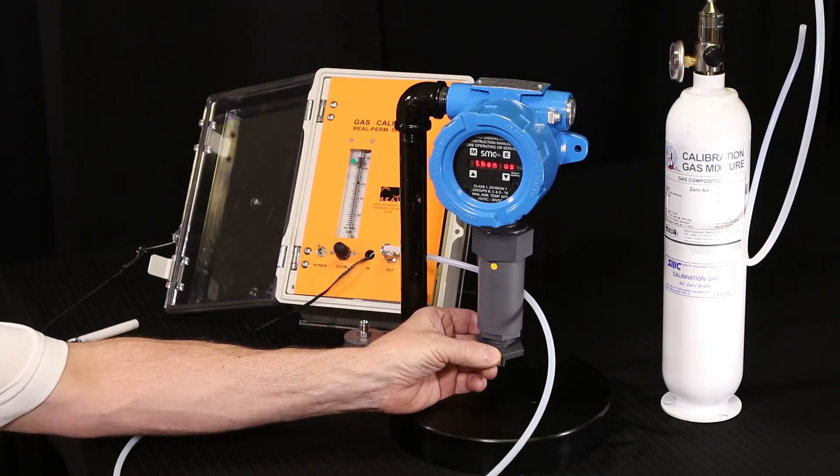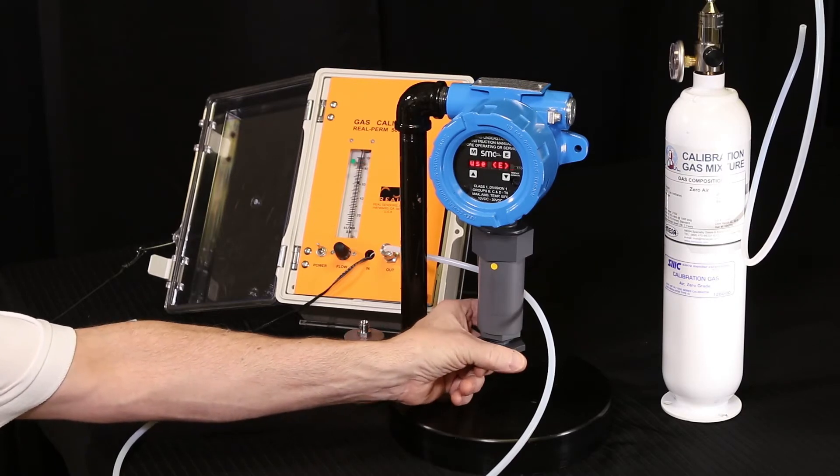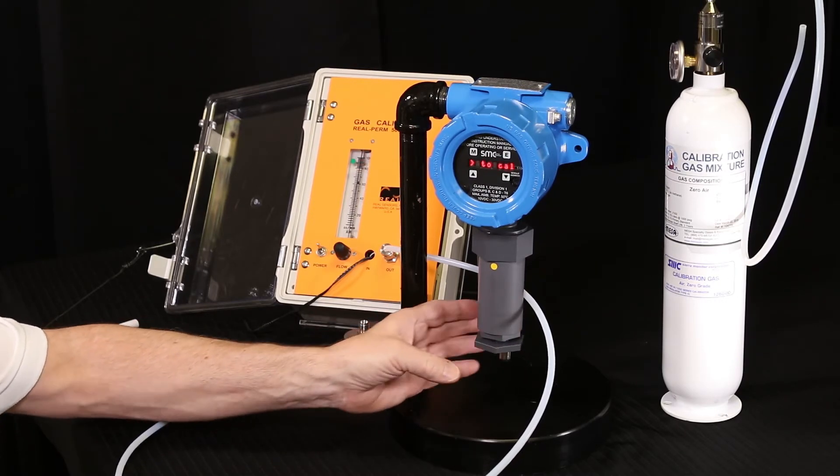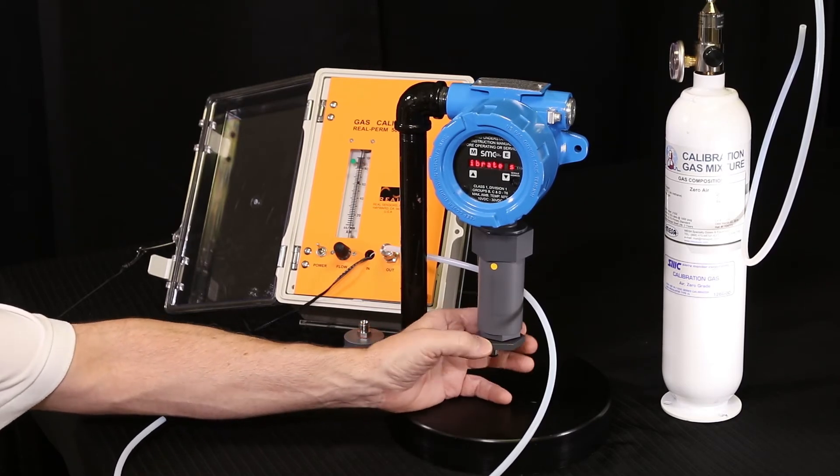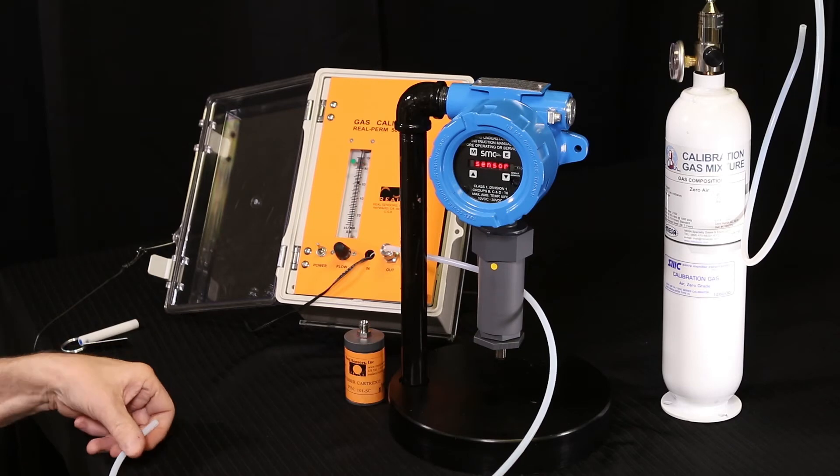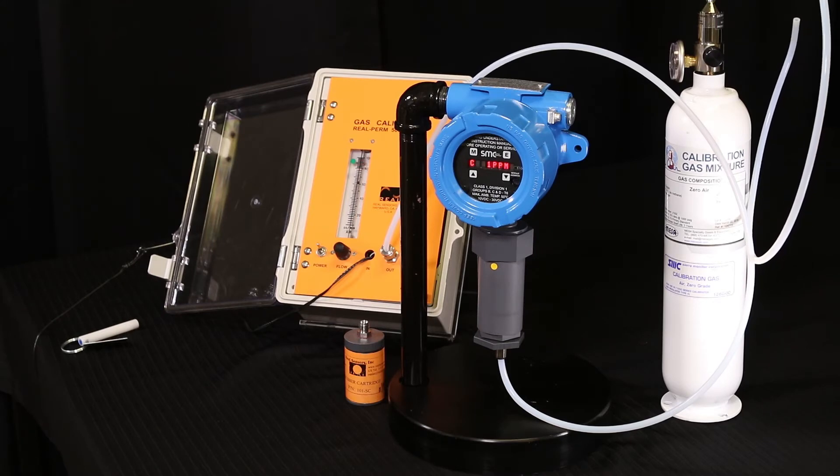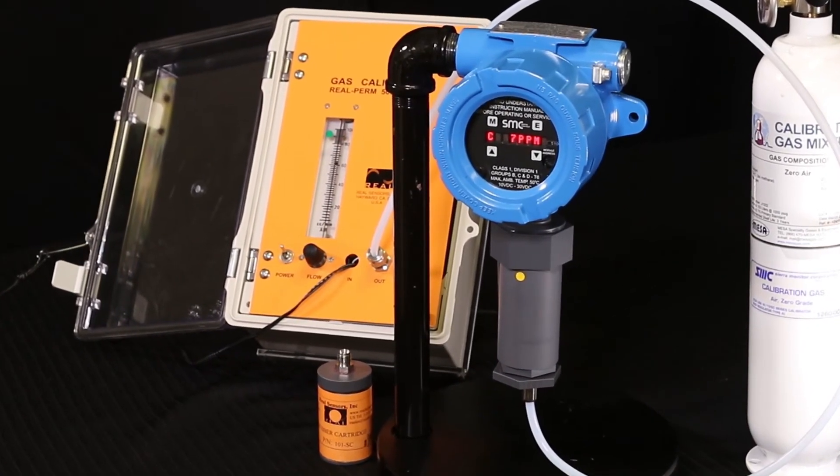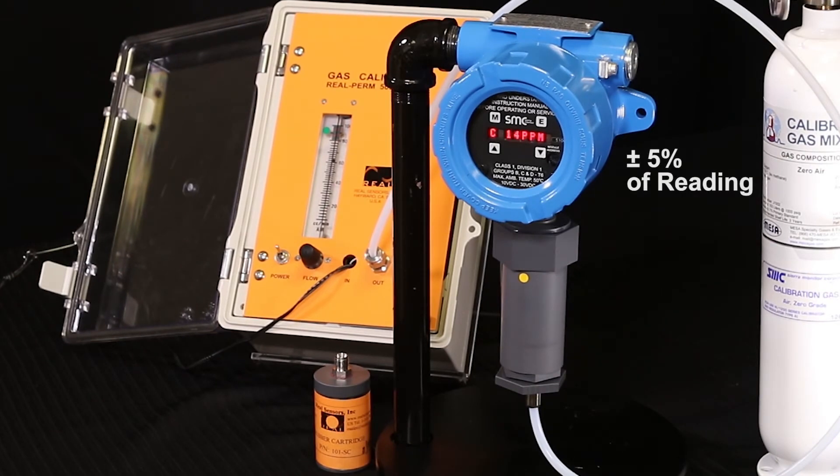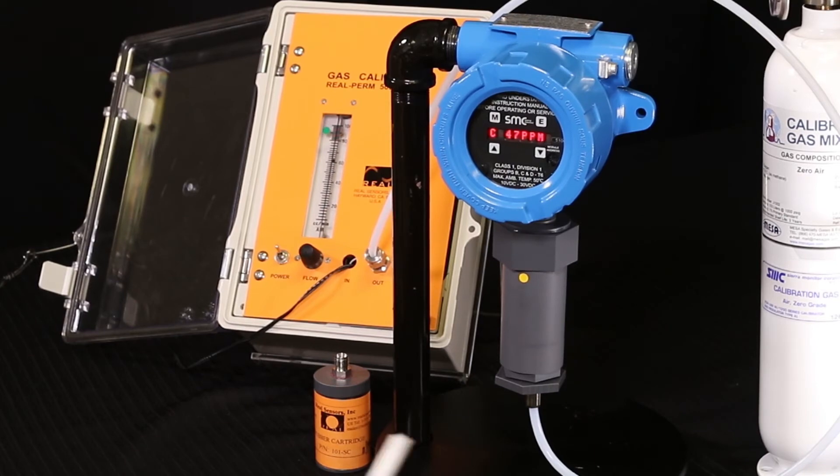Now you are ready to apply the span gas. Attach the gas delivery fitting underneath the detector to the sensor. Then connect the tubing from the permeation system, which is already running, to the delivery fitting and allow the gas to flow into the sensor. This will flow the span gas into the sensor at a predetermined rate. Observe the display so that the concentration remains stable, plus or minus five percent of the reading. Once stable, confirm the calibration by tapping the magnetic wand on the E key.